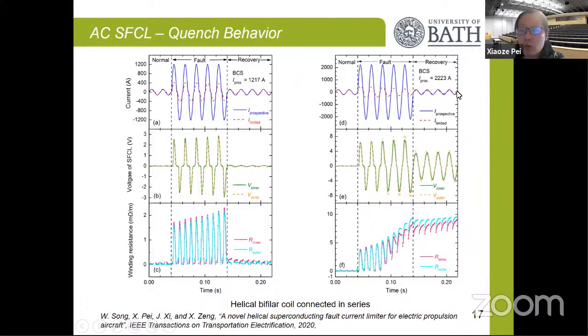And when we double the prospective fault current, increasing it to a higher level, we can see the fault current is limited from 2,200 amps down to a few hundred amps. So this is again very effective fault current limitation. But what happens when we look at the resistance of the superconducting coil, over the 100 milliseconds, is that the superconducting coil limits the fault current.